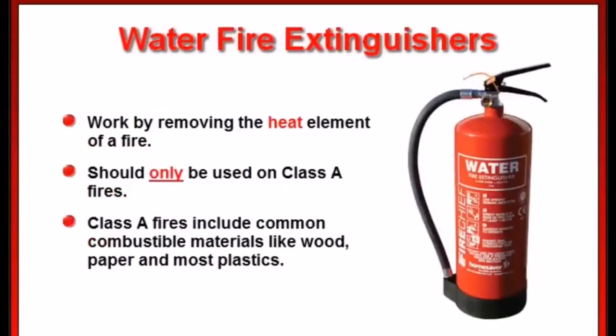Water fire extinguishers work by removing the heat element of a fire. These are for class A fires only, which involve ordinary combustible materials like wood, paper, and most plastics. These fire extinguishers should never be used on a class B or C fire. Class B fires involve flammable liquids like gas, and using one on those could spread the flammable liquid and make it worse. Class C fires involve electrical equipment, and water and electricity don't mix.